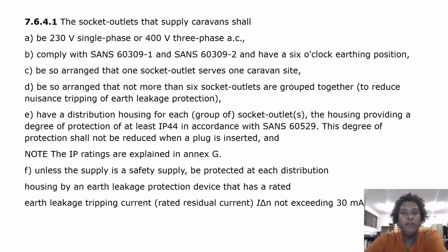The socket outlets that supply caravans shall be 230 volt single phase or 400 volt 3-phase AC, comply with SANS 60309-1 and SANS 60309-2, and have a 6 o'clock earthing position. They shall be so arranged that one socket outlet serves one caravan site, and so arranged that not more than 6 socket outlets are grouped together to reduce nuisance tripping of earth leakage protection. They shall have a distribution housing for each group of socket outlets, the housing providing a degree of protection of at least IP44 in accordance with SANS 60529.